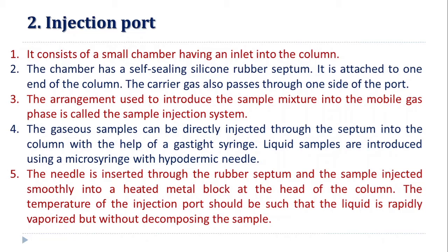Whatever organic sample is there should not be decomposed, because organic substances at a particular temperature decompose themselves. Then the analysis of this decomposed sample will not be useful. For that purpose, you have to set the temperature in such a way that the sample solutes are vaporized or converted into the gaseous form but not decomposed. This is the use of the sample injection port.